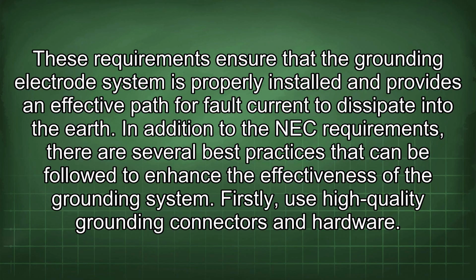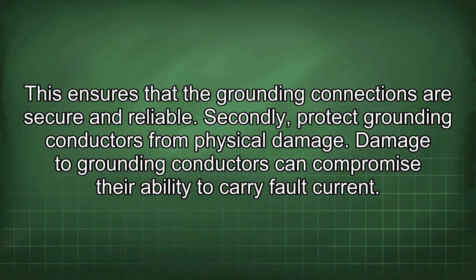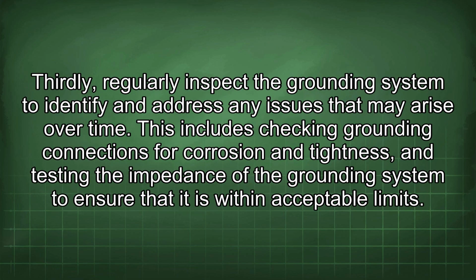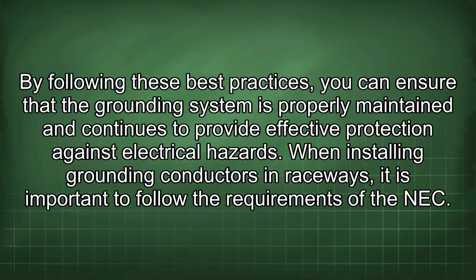In addition to the NEC requirements, there are several best practices that can be followed to enhance the effectiveness of the grounding system. Firstly, use high-quality grounding connectors and hardware. This ensures that the grounding connections are secure and reliable. Secondly, protect grounding conductors from physical damage. Damage to grounding conductors can compromise their ability to carry fault current. Thirdly, regularly inspect the grounding system to identify and address any issues that may arise over time. This includes checking grounding connections for corrosion and tightness and testing the impedance of the grounding system to ensure that it is within acceptable limits.